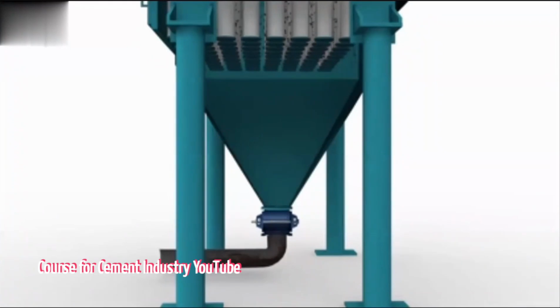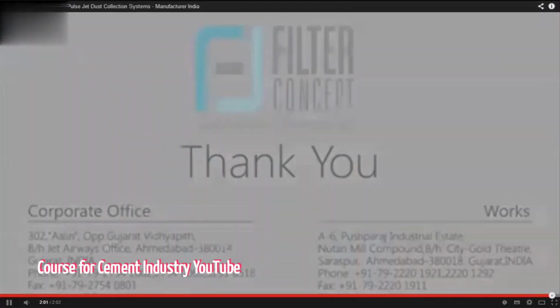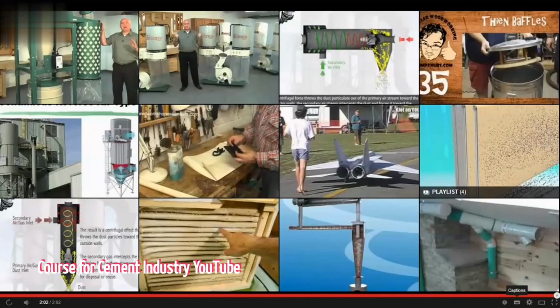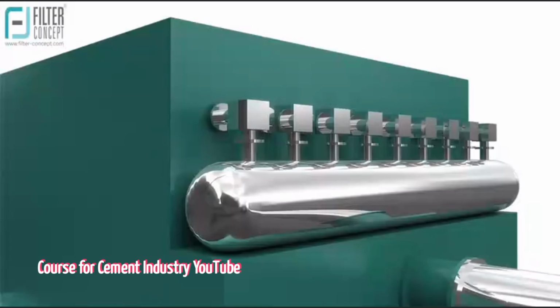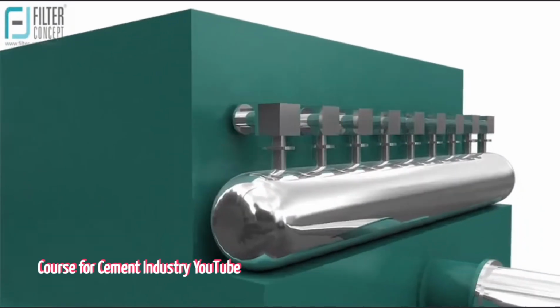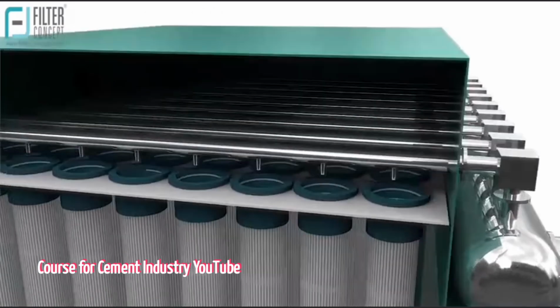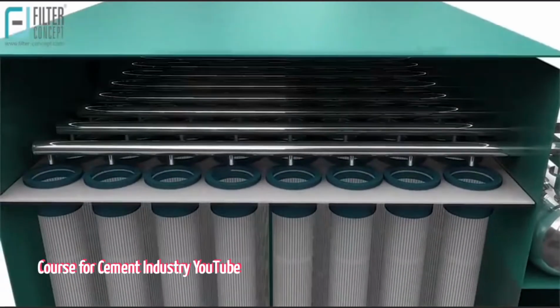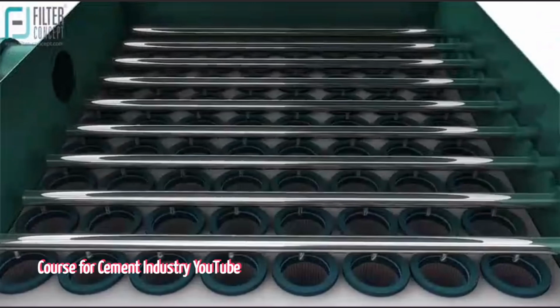That's kind of neat. But surely that can't go on forever. Doesn't it eventually clog everything up? It absolutely does. That's the downside. As the dust cake gets thicker and thicker, it becomes harder and harder for the gas to flow through it. It increases the resistance. Okay, resistance. And that leads us to a really important measurement, doesn't it? The pressure drop. Yes, the pressure differential, or pressure drop. That's the difference in pressure between the dirty side, outside the bag where the dust cake is, and the clean side, inside the bag.